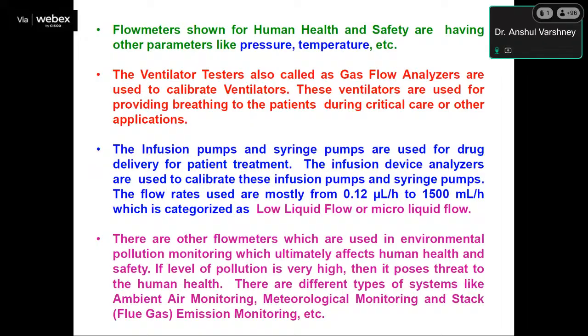The ventilator tester, basically called a gas flow analyzer, is used to calibrate ventilators. These ventilators are used for providing breathing support to the patient during critical care or other applications. The infusion pumps and syringe pumps are used for drug delivery for patient treatment. The infusion device analyzers are used to calibrate these infusion pumps and syringe pumps. The flow rates used are mostly from 0.12 microliter per hour to 1500 milliliter per hour, which is categorized as low liquid flow or micro liquid flow. At NPL, we have this low liquid flow calibration system, and its range is from 1 ml per hour to 1500 ml per hour.